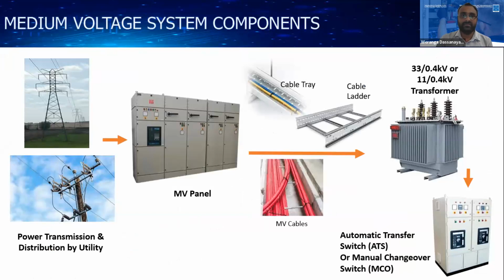Here, this is how medium voltage system components are installed in the system. First, you have the transmission line which comes from the power station or the national grid. That transmission line feeds mainly a medium voltage panel in your premises.